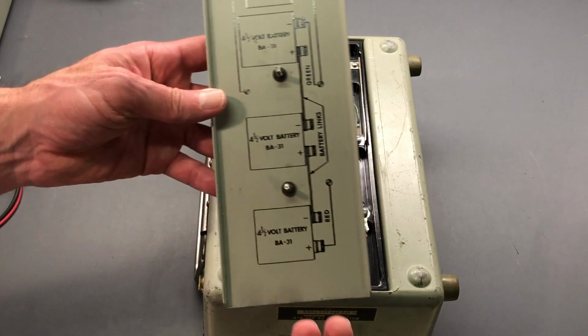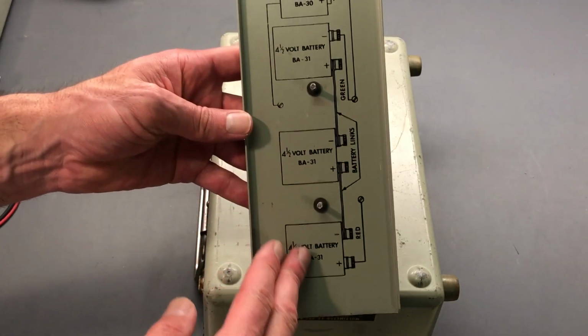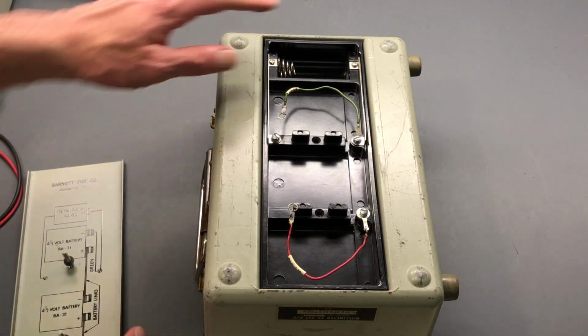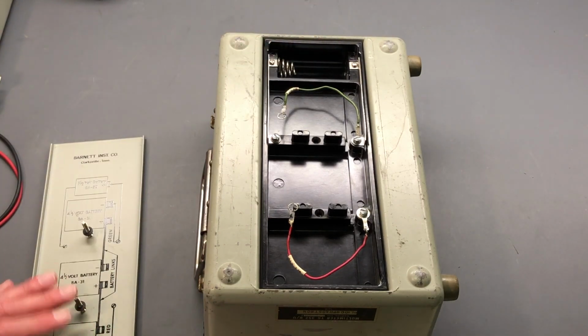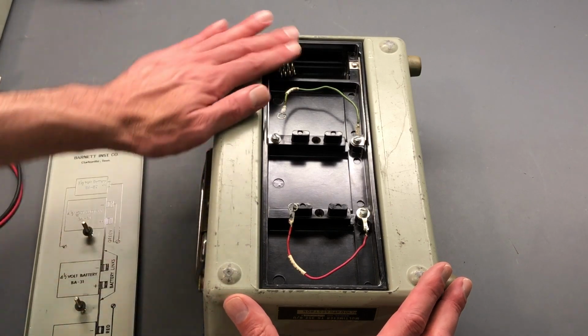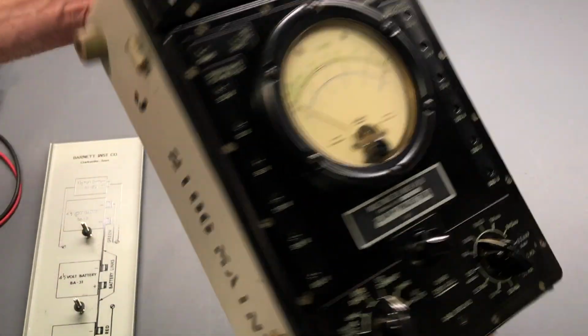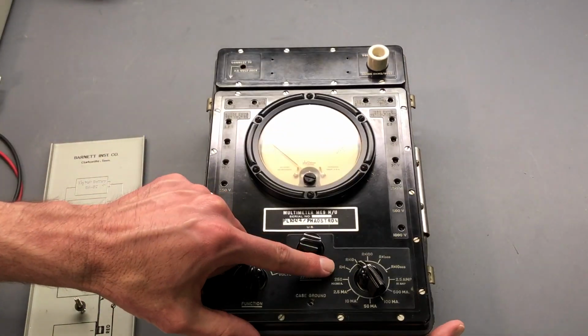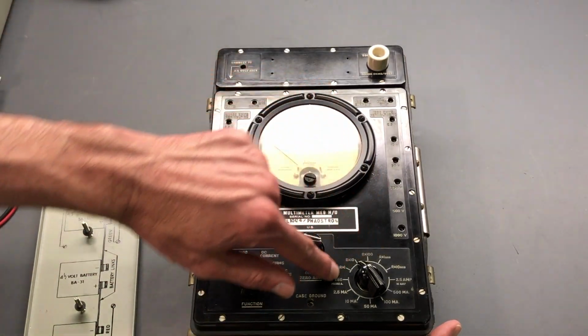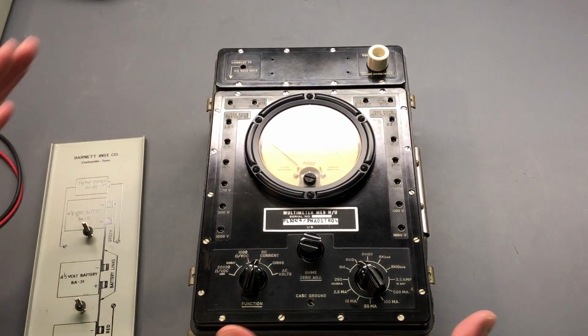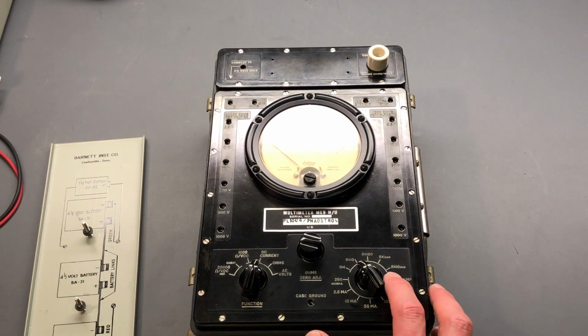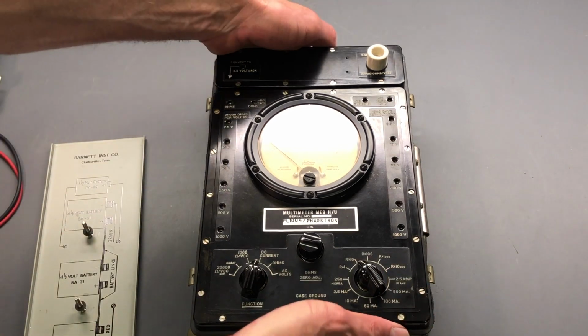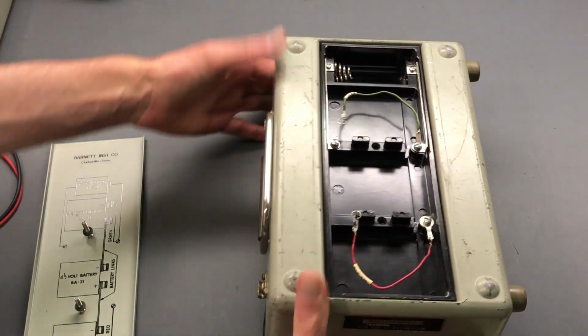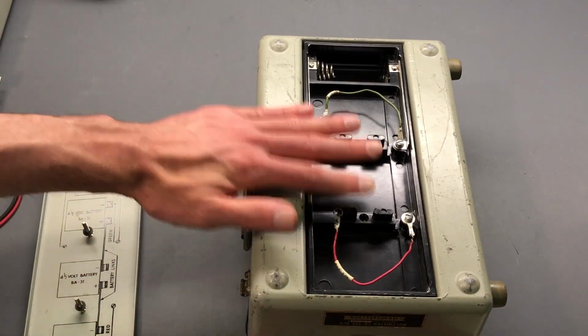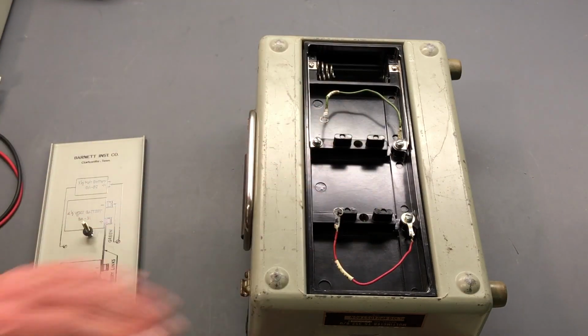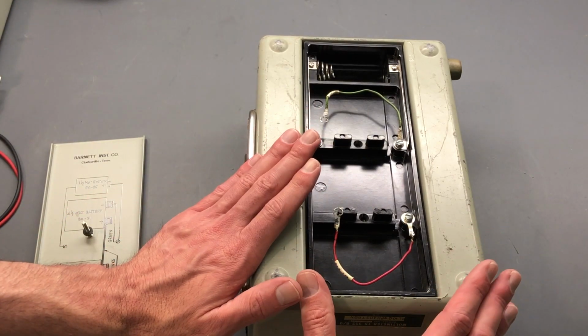So the question is, what can we do to replace these 3 batteries? First, if you install the D cell battery up here, you'll find that most of the ohms functions actually work. With just the D cell installed, the R times 1 through R times 1000 ranges will function correctly. So just one battery gets you some functions. But the R times 10,000 range requires all the batteries to be installed. These 3 batteries plus the D cell must all be installed for the highest ohms range to function correctly.